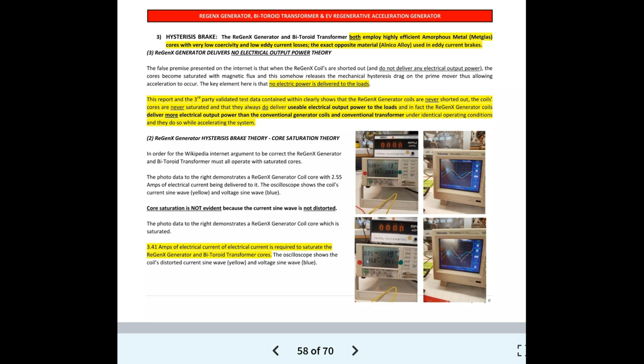2. ReGenX generator hysteresis brake theory, core saturation theory. In order for the Wikipedia internet argument to be correct, the ReGenX generator and Bi-toroid transformer must all operate with saturated cores. The photo data to the right demonstrates a ReGenX generator coil core with 2.55 amps of electrical current being delivered to it. The oscilloscope shows the coil's current sine wave, yellow, and voltage sine wave, blue. Core saturation is not evident, because the current sine wave is not distorted.